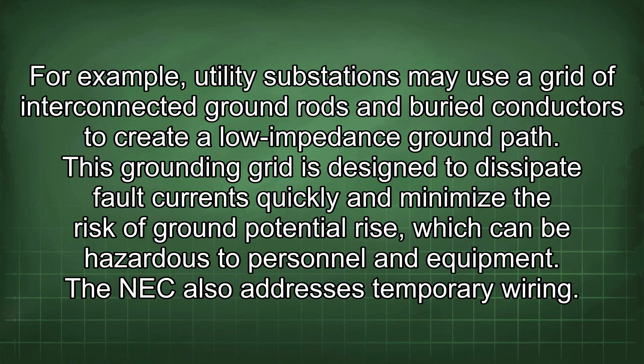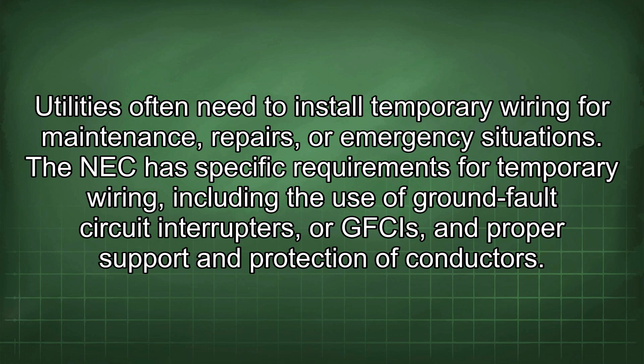The NEC also addresses temporary wiring. Utilities often need to install temporary wiring for maintenance, repairs, or emergency situations. The NEC has specific requirements for temporary wiring, including the use of ground fault circuit interrupters, or GFCIs, and proper support and protection of conductors. Utility companies typically have their own procedures for temporary wiring that may differ from the NEC requirements in some respects. These procedures are designed to ensure the safety of workers and the public while minimizing the risk of electrical hazards.